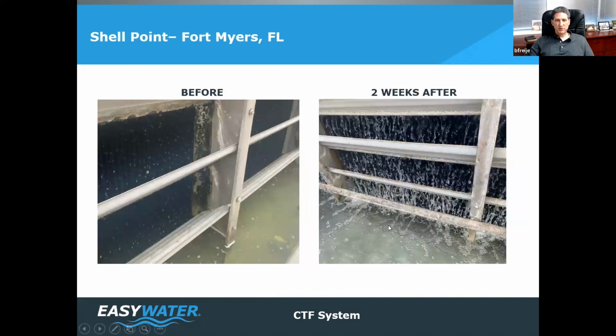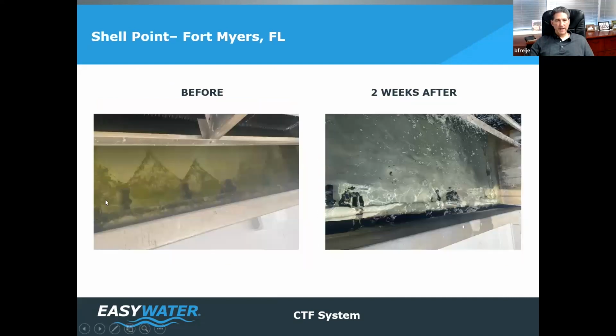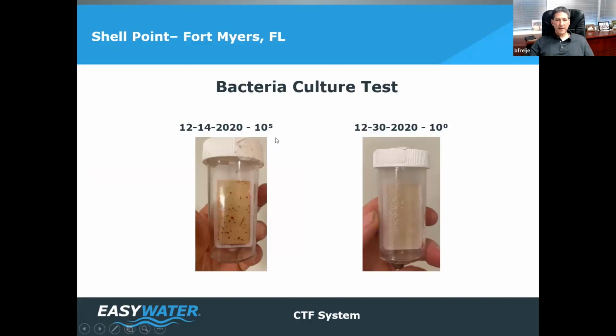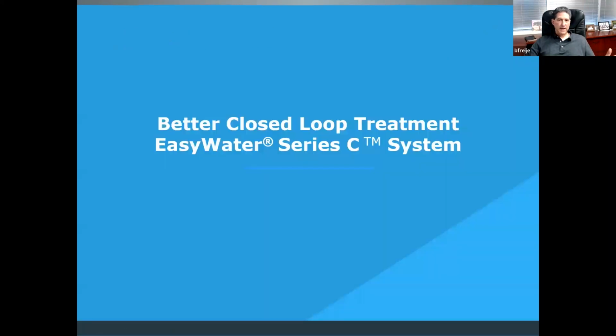Two-week results: in two weeks, the water's crystal clear, algae on the fill completely gone, algae in the basin where sunlight hits completely gone in two weeks. Why? It's alive, it requires food to live, and we literally starve it. Bacteria count 10 to the 5th, which is typical. Cooling towers operate at 10 to the 4th or 10 to the 5th, but in 13 days, 10 to the 0. So, last thing really to talk about, closed loops.